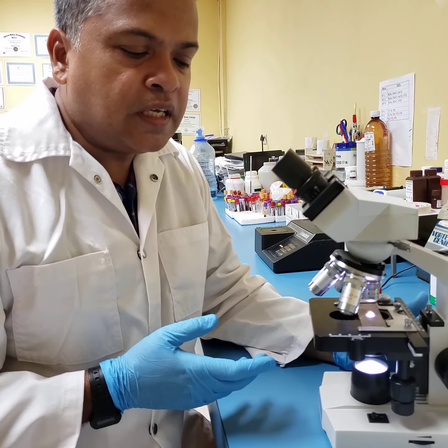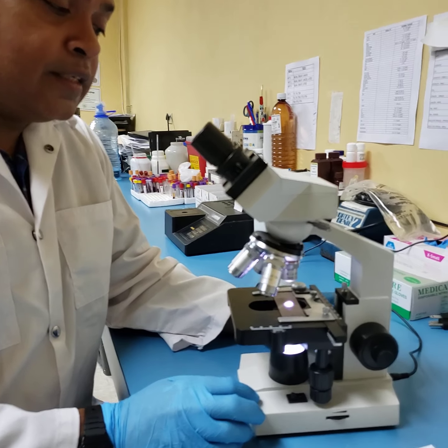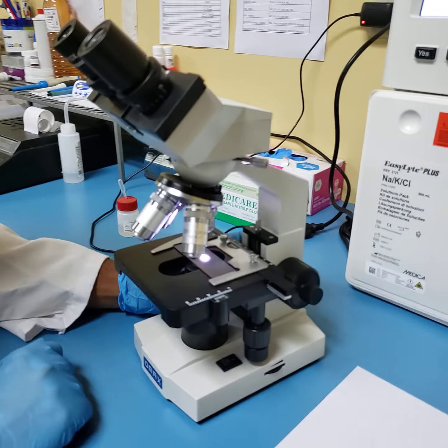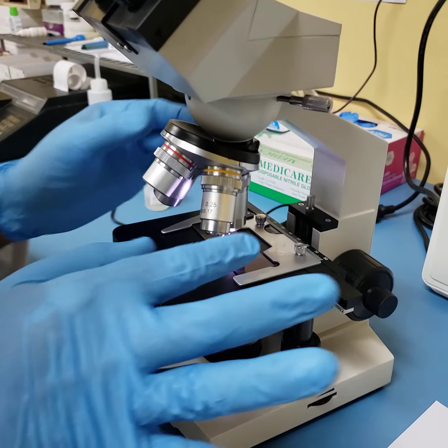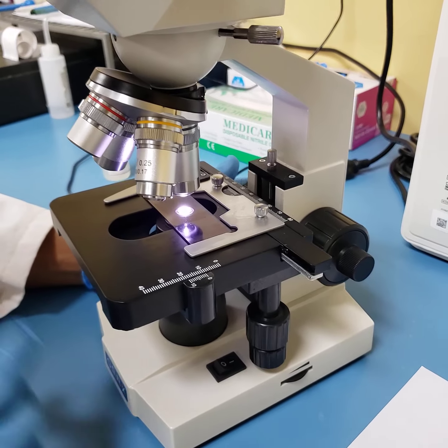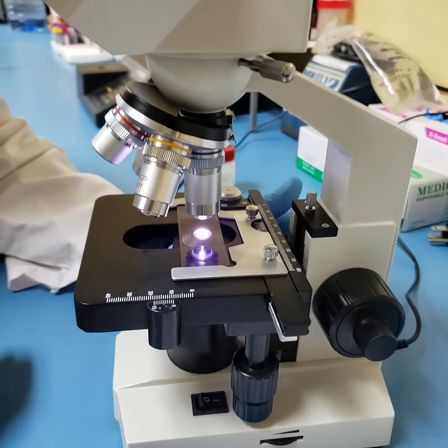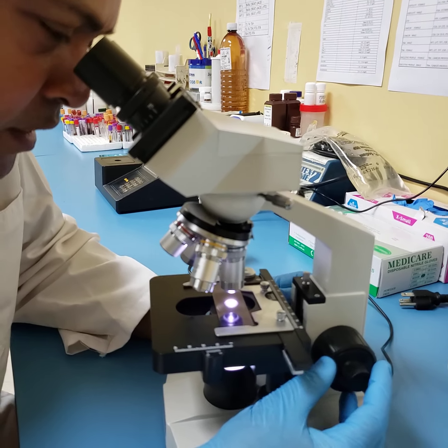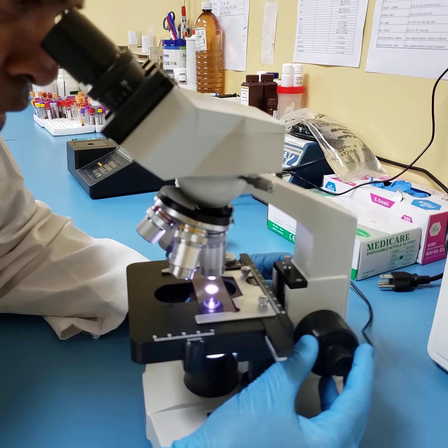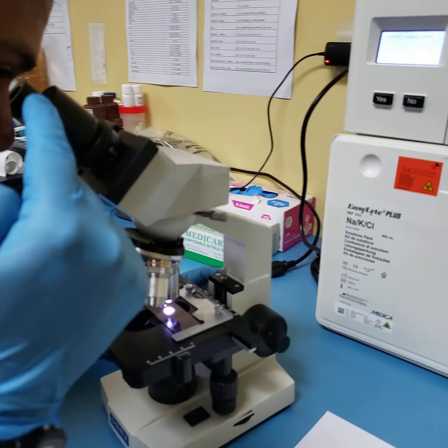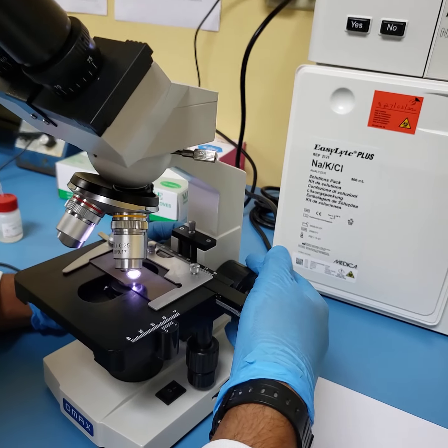What some persons do, which is very risky and you can break your slide in the process, is they don't do that. They start with their stage straight down. Then they flick into place any lens that they want to examine the image with.